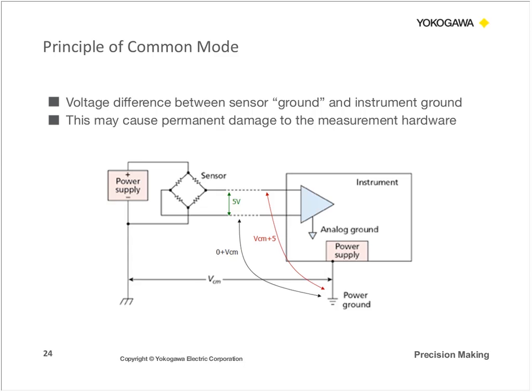So as you can see, for example, you have some voltage going between the sensor, and there is a common mode voltage that occurs between the two inputs of the differential amplifier in reference to the power ground. And this can really cause permanent damage to the measurement hardware, because typically common mode voltage will run into the hundreds and thousands of volts. And in practical test and measurement situations, the common mode voltage is obviously going to exceed the instrument's amplifier input rating. That input rating is typically about 10 volts, and so it's very low. So we need to be able to isolate the common mode voltage from the instrument's internal amplifiers.